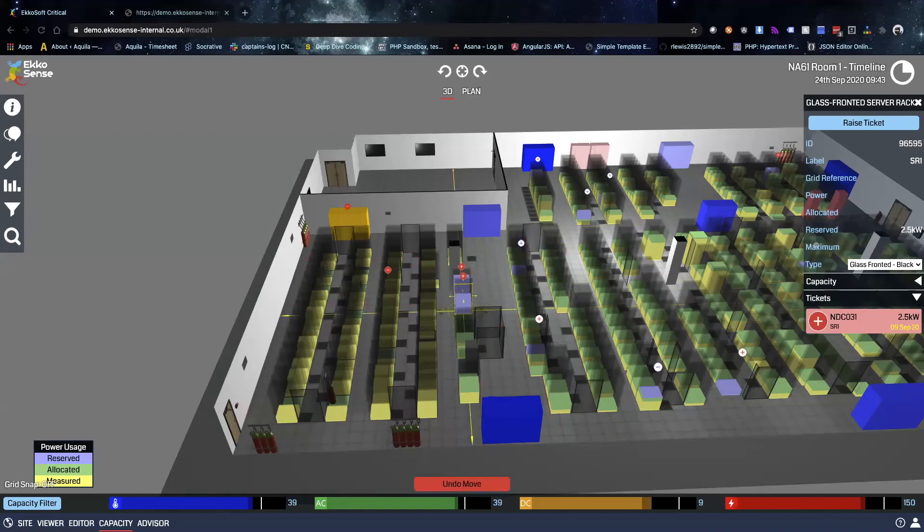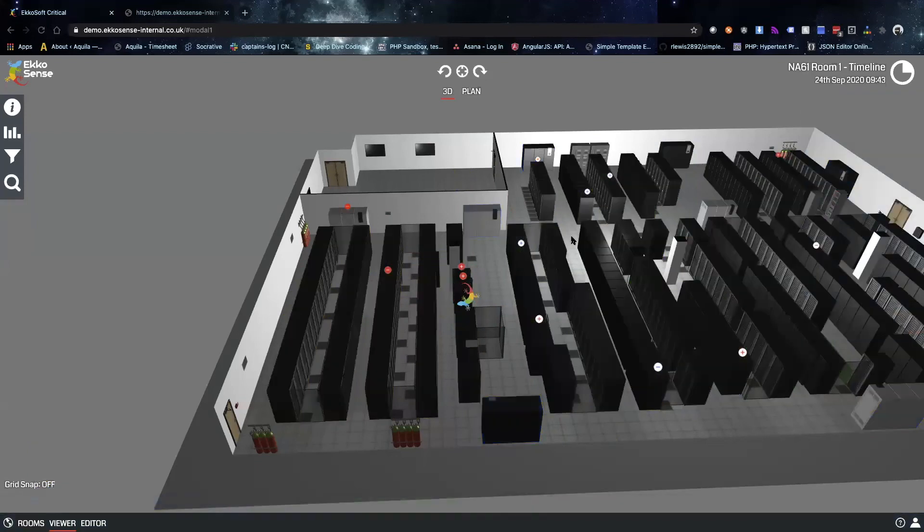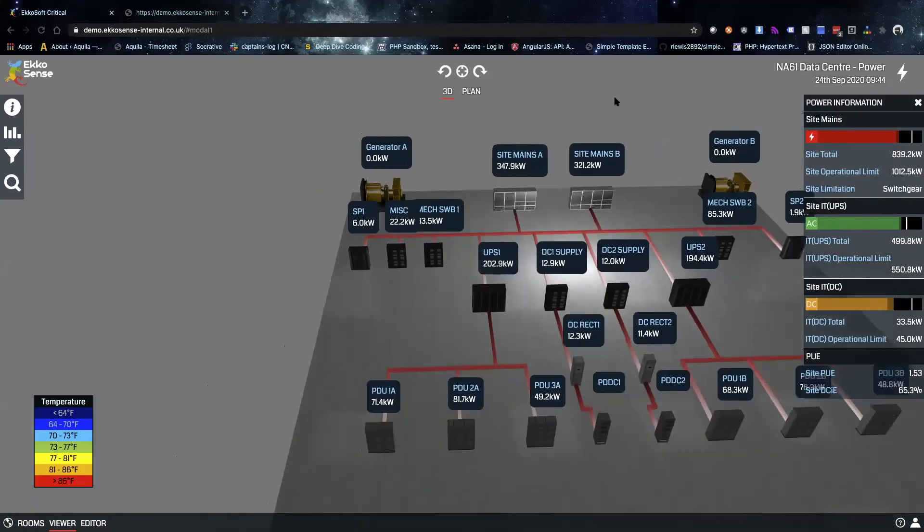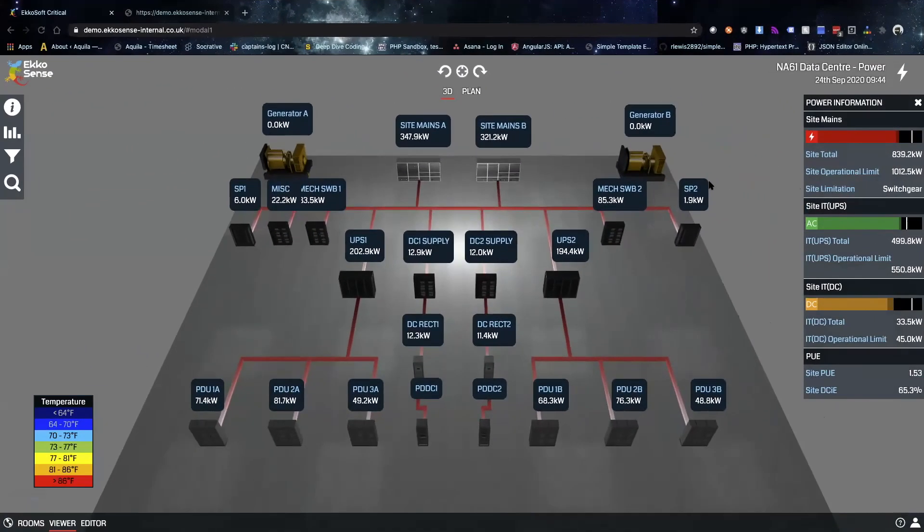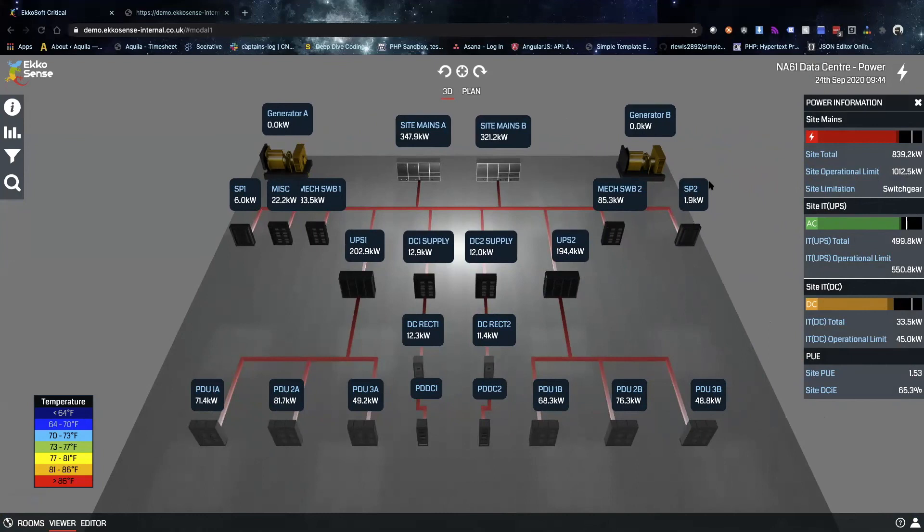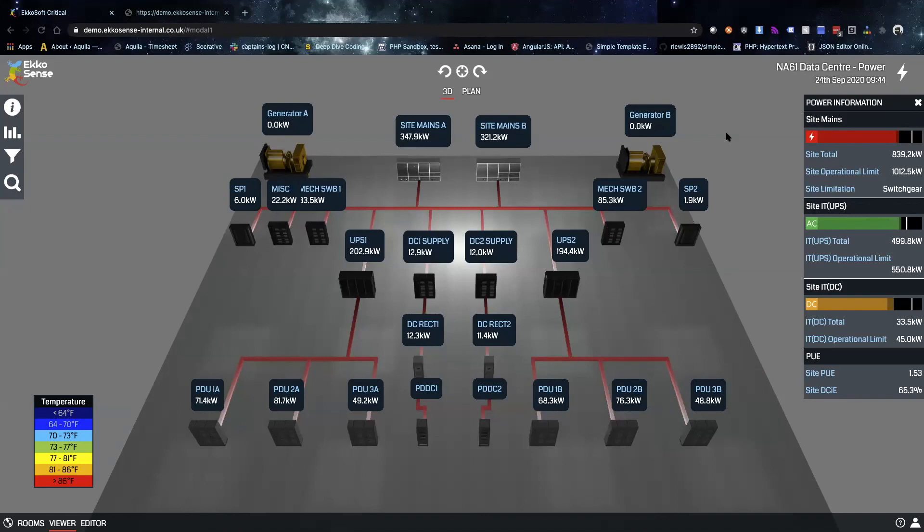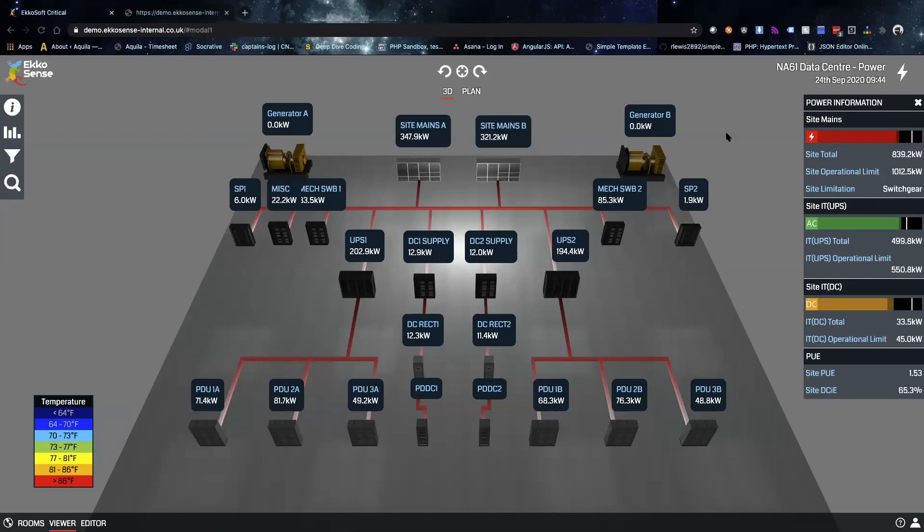We're going to take a look at one more view, which is the site power view. We're focusing on the cooling thermal and the optimization side here, but Travis has kindly just touched on some of the capacity management side. Intrinsically linked to that is the ability or requirement to pull in the power data. We have a lot of customers that use or replace existing EPMS type systems or just use the visuals from our power views here. The ability to pull power data from existing power loggers—we don't supply power loggers, we just pull data usually by Modbus, occasionally from SNMP down at the rack level.